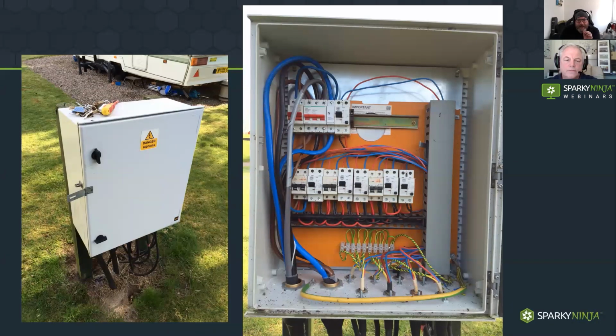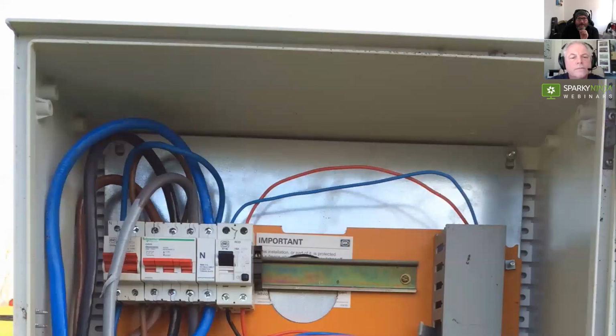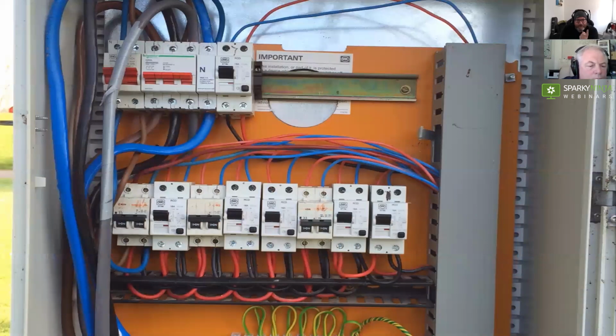But then also just taking out of L2, I think it is, you can see the top of the black there is a feed to the double pole switch to the left. So that's feeding this panel, and that then goes down to this little mess where we're looping to a double pole MCB, which caravan parks require double pole in case, obviously, the person putting in the hookup point has made up their lead with reverse polarity. Yeah, so caravan parks should have double pole protection on an MCB in case your hookup lead is of reverse polarity, basically. But what we can see here is we've got a loop into a double pole MCB that leads into an RCD, then leads to another. And so we've got this loop underneath and then up to the top one.